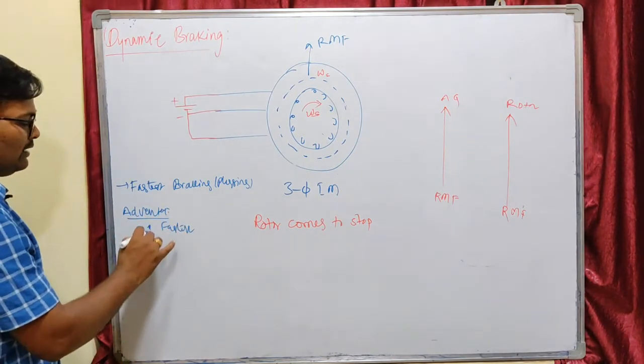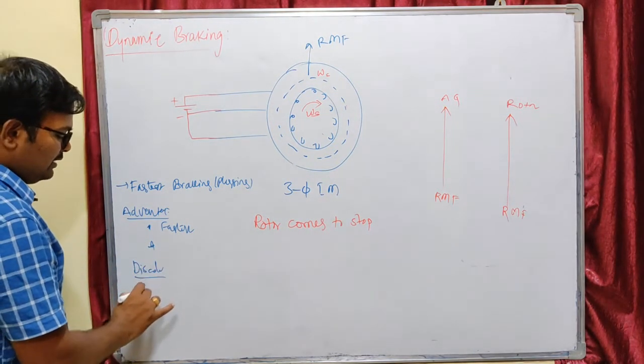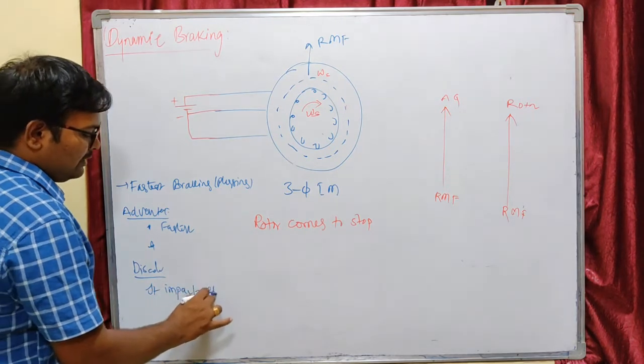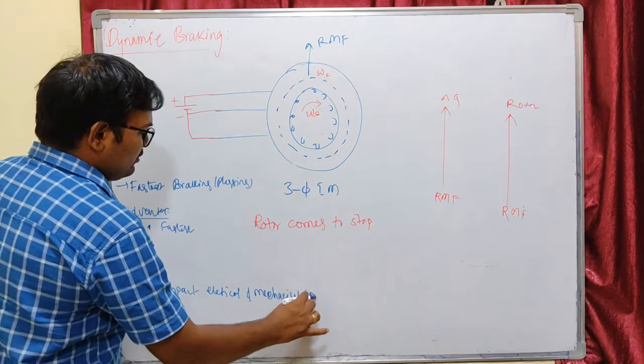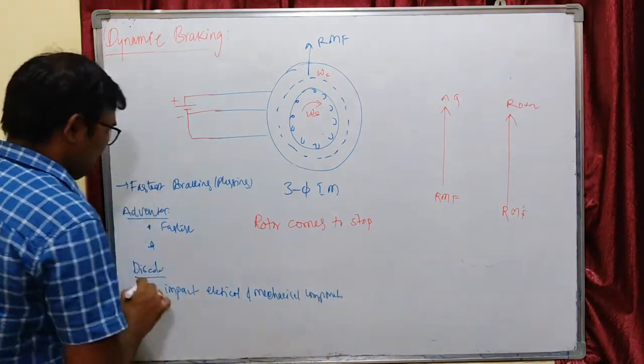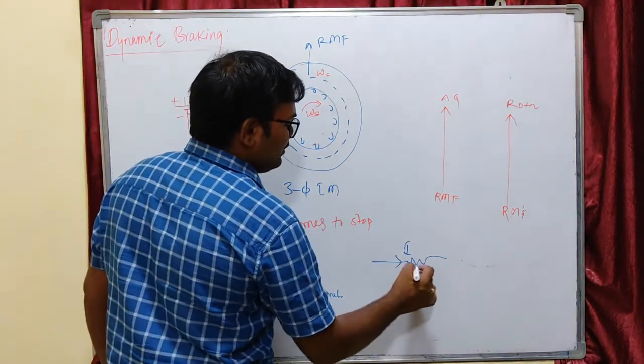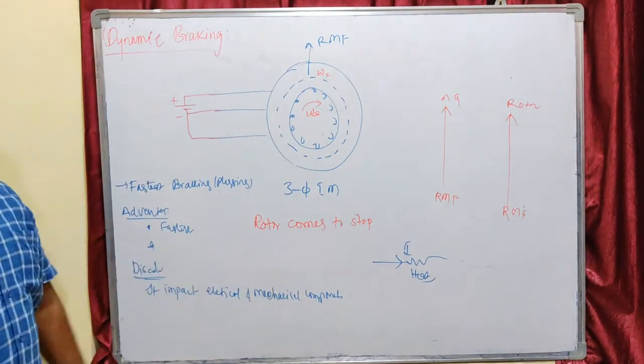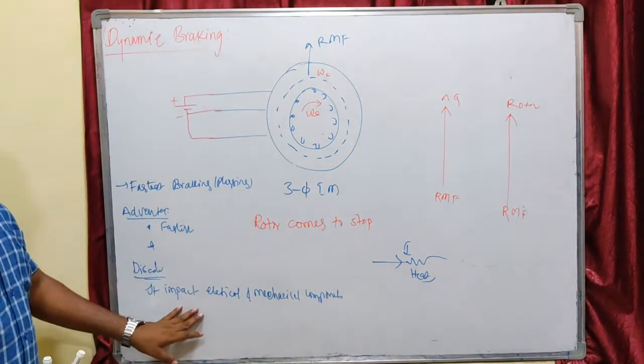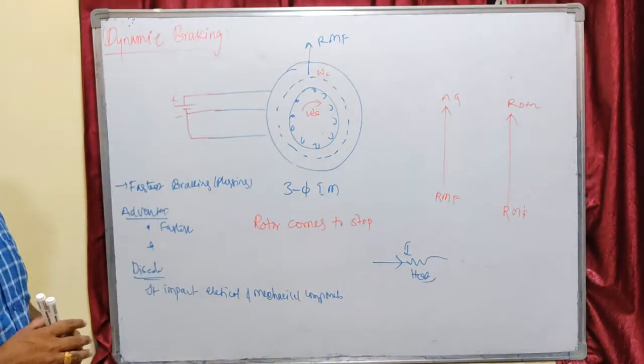Plugging can be useful for emergency stops. The disadvantages are that it impacts electrical and mechanical components heavily. There is a huge current flow in plugging mode that produces much heat in the resistors, so plugging is used only under very rare conditions. This concludes dynamic braking and the braking of machines overall.